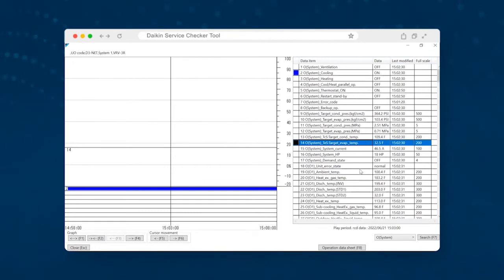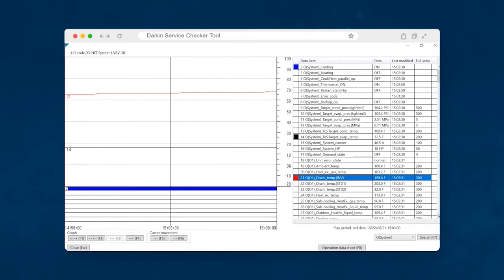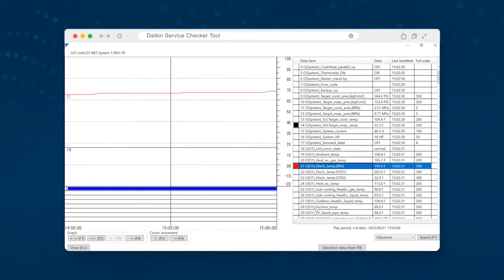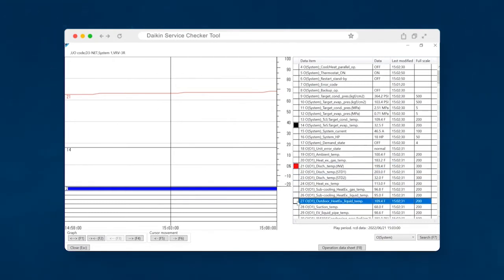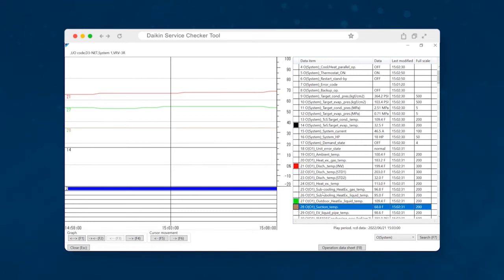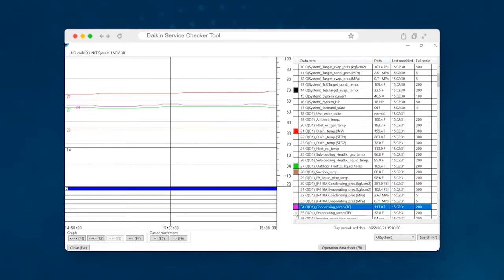The next thing that you'll want to take into consideration is the discharge inverter temp. And we'll get to why that's important in a minute. You can also check the discharge standard temp, but both of these generally are going to be pretty close to the same, assuming that you don't have an oil return issue, which we will also discuss later. Another pertinent piece of information will be the outdoor heat exchanger liquid temp and the suction pipe temp. And then finally, we have the condensing temp and the evaporator temps.